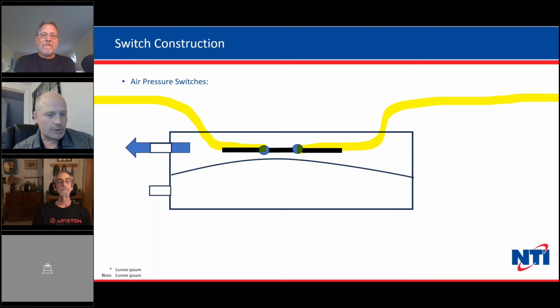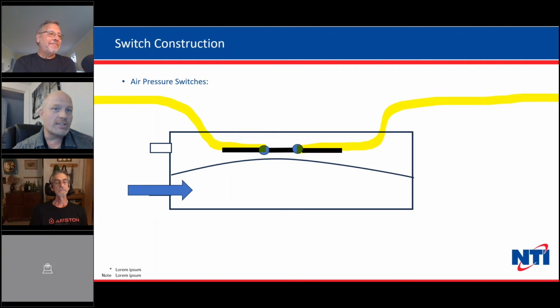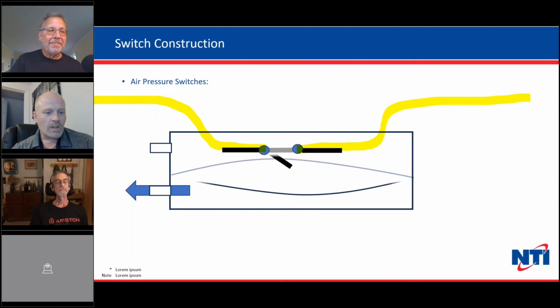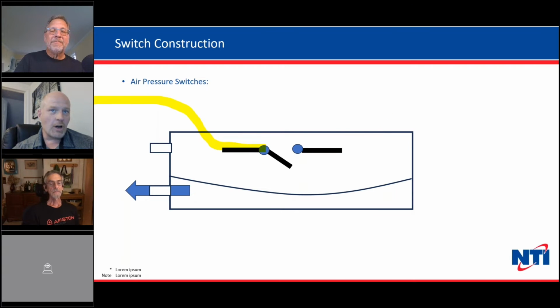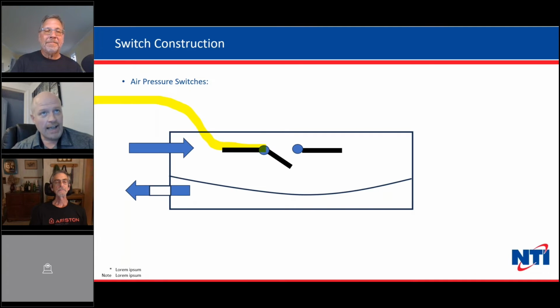If you were to have a single tube hooked up to your air switch, like the old T series, for anybody that's been around that long, we used to use a single tube on that air switch, and we actually didn't use the suction. What we used was the positive pressure that came off the blower, and it would blow into the one side of the switch and trigger it to activate and allow the boiler, the Sentry in this case, to fire the burner. Of course, if you create suction on what should be the positive side or create positive pressure on what should be the negative side, the switch will do the opposite.